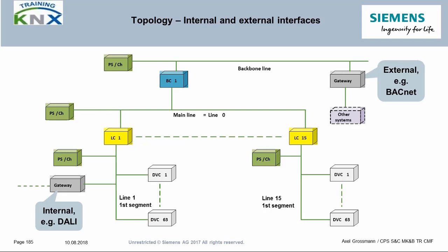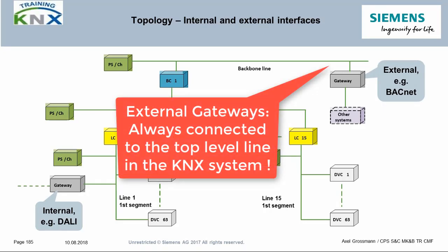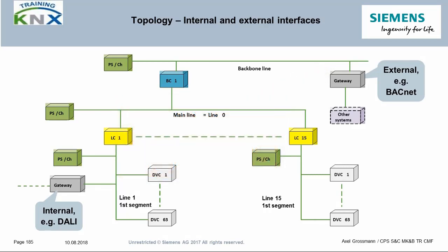Internal and external interfaces. Every open communication system must be networkable with other systems — this is also the case with KNX. The connection devices used to exchange data in both directions are called gateways. Gateways work like interpreters: they know both bus languages and can, according to a regulation, transfer data from one system to the other by reformatting and addressing it accordingly. Such gateways can be located anywhere in the system; however, they should be installed at the highest hierarchy level if they are external, so that all network structures can be reached at the same speed and there is no telegram overload on the sublines.